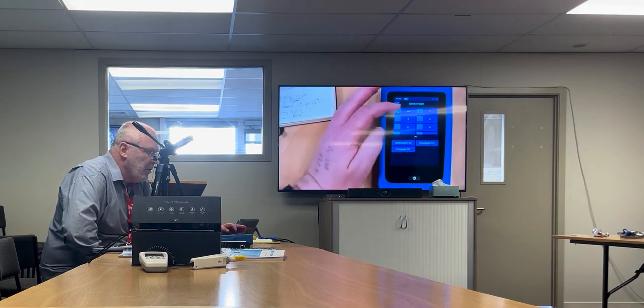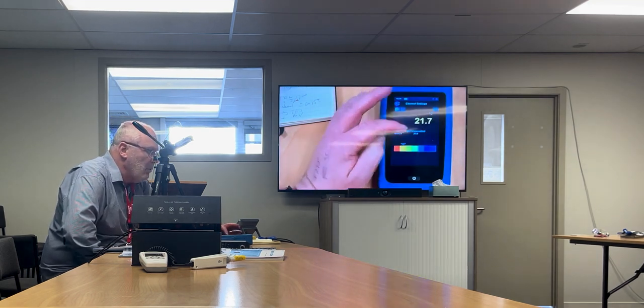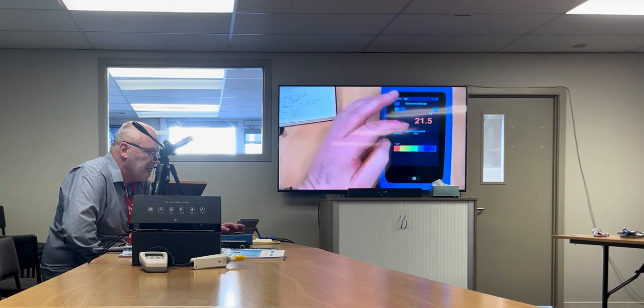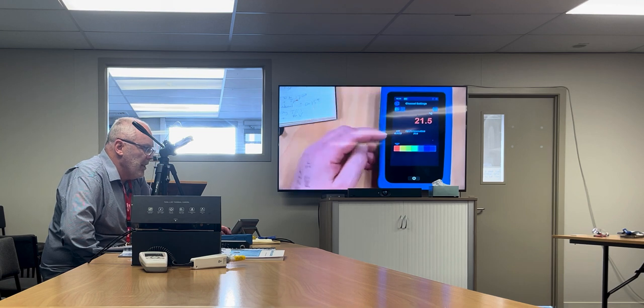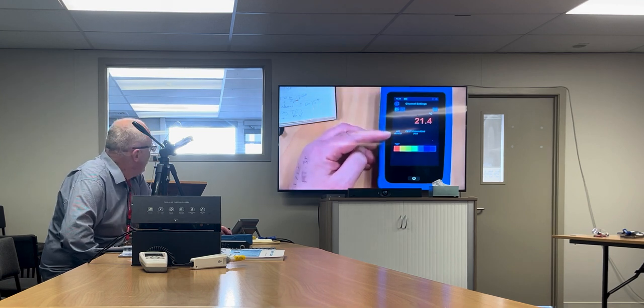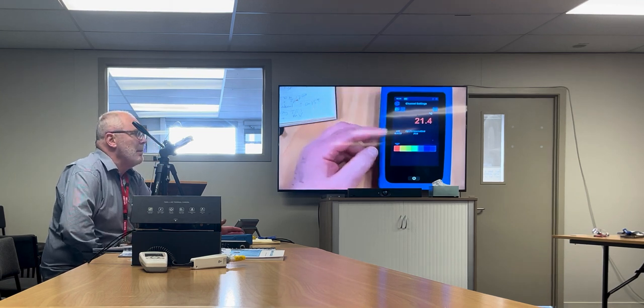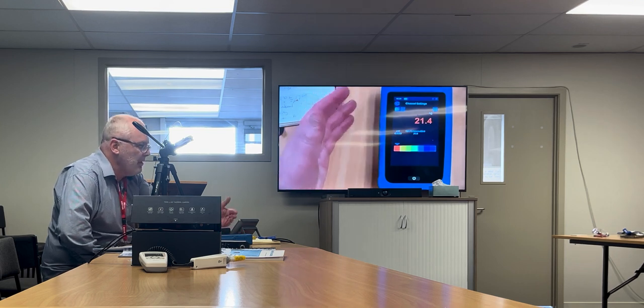So we've got an industrial thermocouple on channel A. We'll make it whatever colour we want to make it for our chart. You can see now it's reading 0.031 millivolts, which if you look up the thermocouple table, you can see that a K-type at that temperature is there.